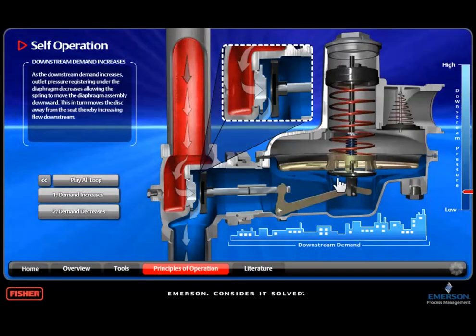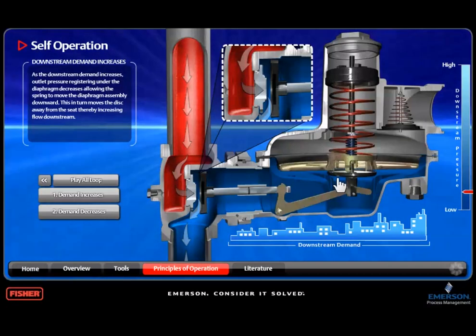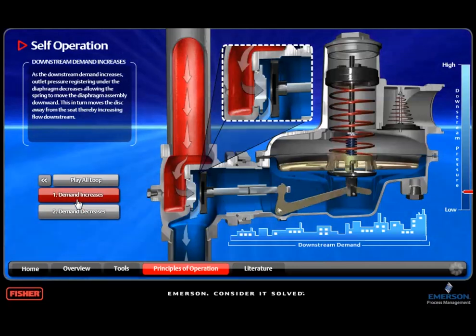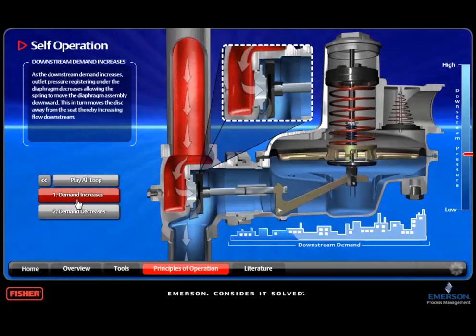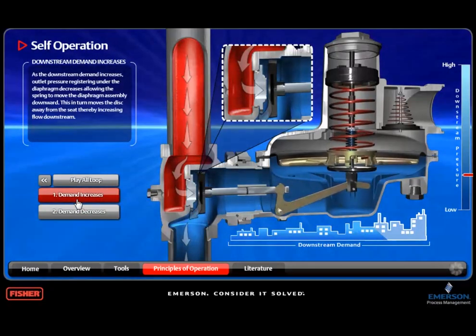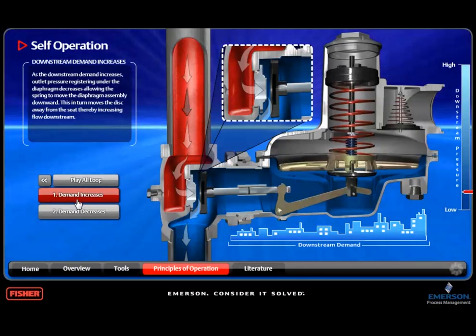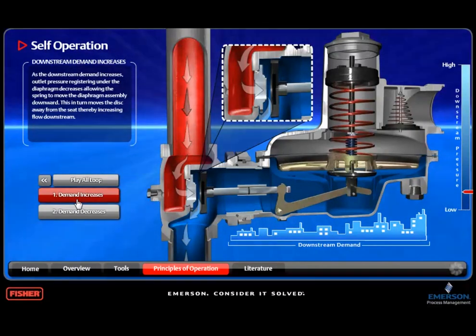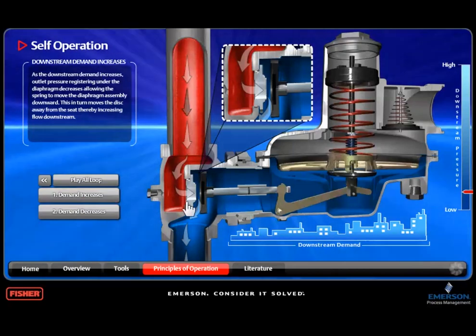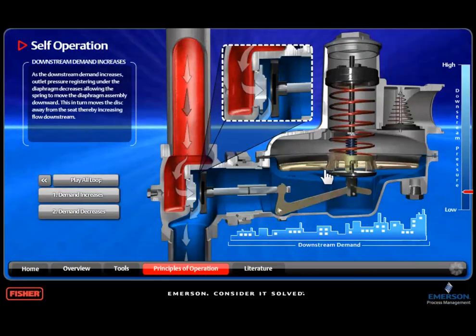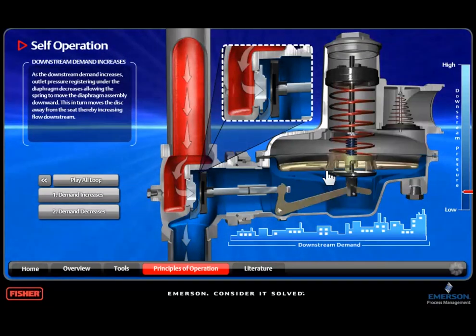Now that we understand what makes a regulator operate, let's look at what's happening inside the regulator while it's installed on your commercial building. If the regulator senses decreasing outlet pressure due to an increase in flow demand from your building's heater or other equipment, the subsequent force change on the diaphragm will move it downward and pull the valve plug away from the orifice, resulting in additional flow to match the increased demand.